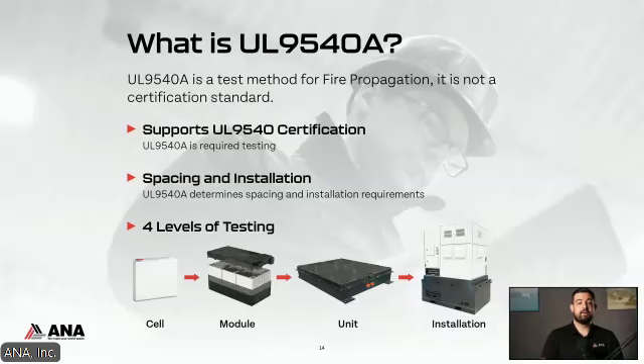So what is 9540A? This is the one I brushed over earlier. So 9540A is a test method for fire propagation, and it's not a certification standard. You cannot obtain certification to 9540A. This is required for 9540. This testing you must undergo on your battery system. This testing determines system level install instructions such as spacings, whether it's unit to unit, energy storage system to energy storage system, or it could be the unit and a building or wall or some other form of enclosure.